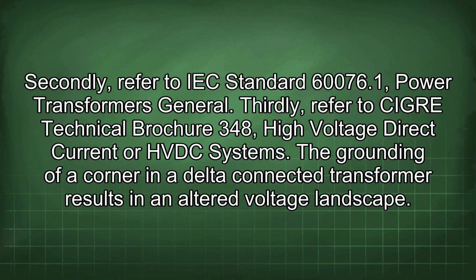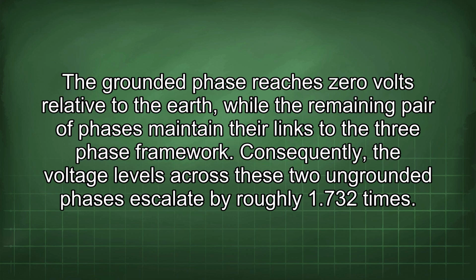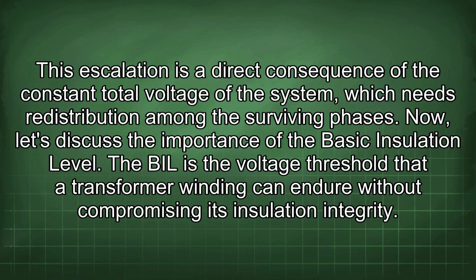The grounding of a corner in a delta-connected transformer results in an altered voltage landscape. The grounded phase reaches 0 volts relative to the earth, while the remaining pair of phases maintain their links to the three-phase framework. Consequently, the voltage levels across these two ungrounded phases escalate by roughly 1.732 times. This escalation is a direct consequence of the constant total voltage of the system, which needs redistribution among the surviving phases. Now let's discuss the importance of the basic insulation level.